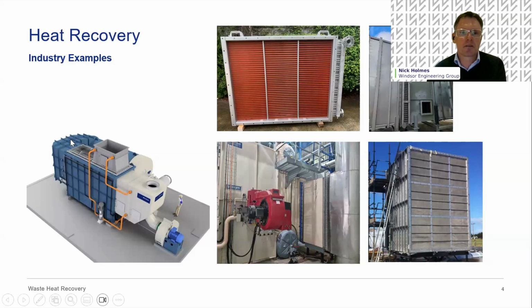This photograph, it's a solid model, sorry, of a new development where we link a heat recovery coil in the exhaust stream. This is a process heater, a gas-fired air heater. So there's a flue gas typically here. We put a heat recovery coil in this section to recover some exhaust heat, and then a simple water loop with a pump to a secondary coil, which is an air preheater. So again, it's a simple closed loop system: recover some heat, put it back into the process air to add up to 7% efficiency to the heater.